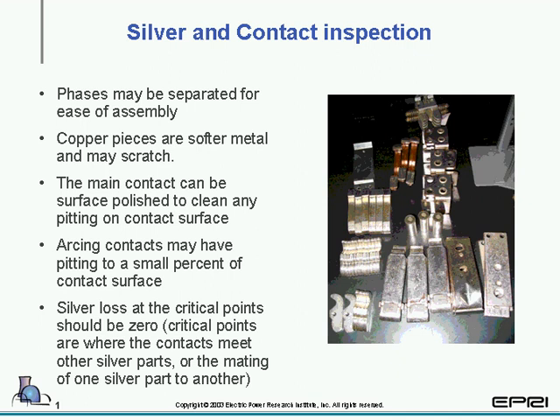So that's basically, we took a look at cleaning. Now we're going to take a look at inspections. You want to inspect the copper pieces or any type of silver-plated copper pieces, or any type of removal of the silver. Some manufacturers have a 0% silver loss on the copper or conductive carrying pieces. And as in the picture, you will see that the parts are inspected after the cleaning.